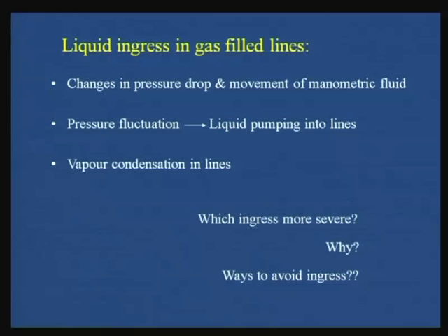But the good part is, see, in the manometer the movement of the liquid is much more vigorous. Okay, so therefore, the pumping action is much greater there. Here the diaphragm moves to a very small extent. So therefore, the pumping action is not so high, and the ingressing of the second fluid into the manometer line is not so serious either. Okay, but for differential pressure we usually always use liquid filled lines, just in order to minimize the pressure fluctuation part.